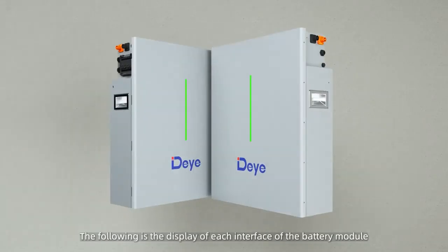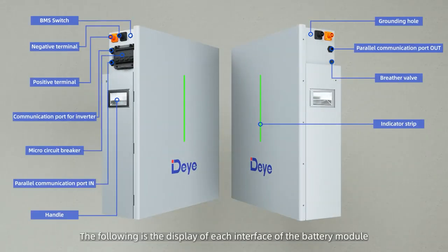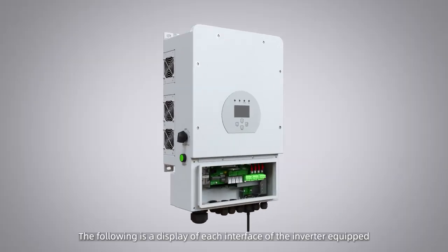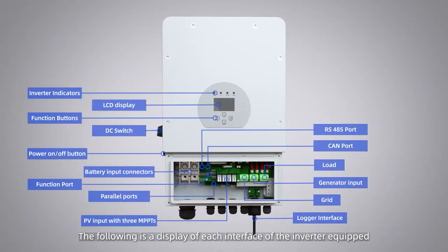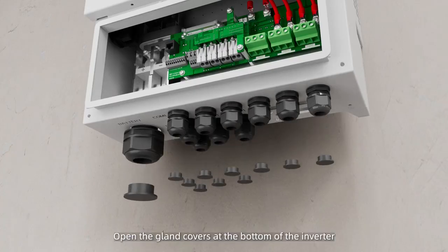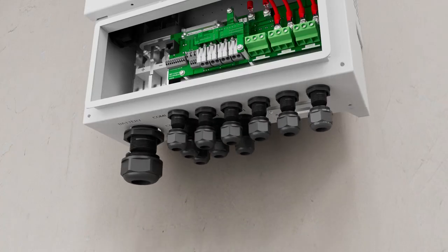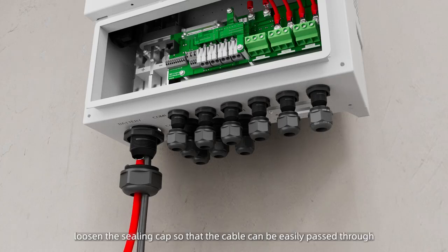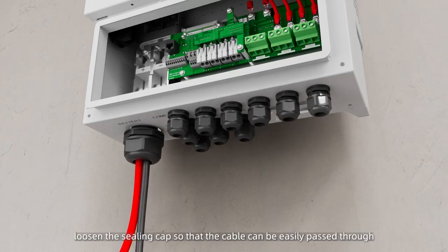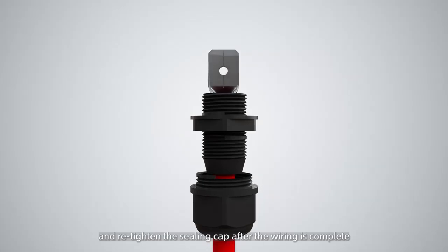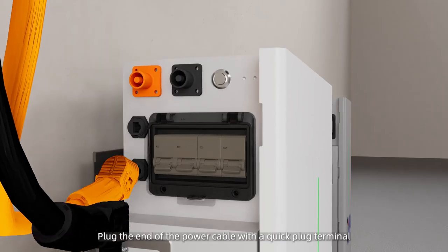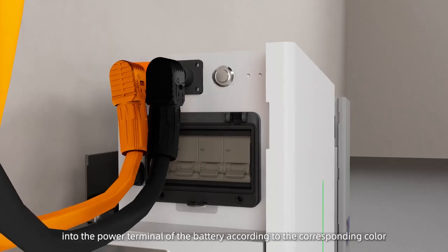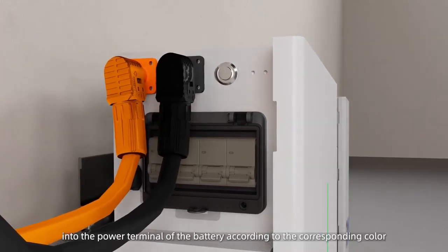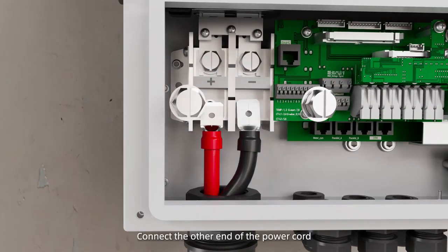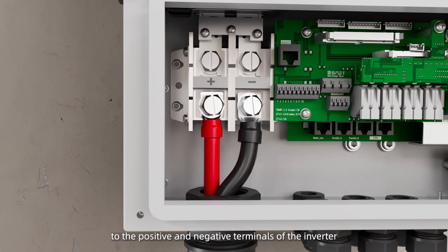Cable connection. The following is the display of each interface of the battery module. The following is a display of each interface of the inverter equipped. Open the gland covers at the bottom of the inverter. When wiring, loosen the sealing cap so that the cable can be easily passed through, and retighten the sealing cap after the wiring is complete. Plug the end of the power cable with a quick plug terminal into the power terminal of the battery according to the corresponding color. Connect the other end of the power cord to the positive and negative terminals of the inverter.